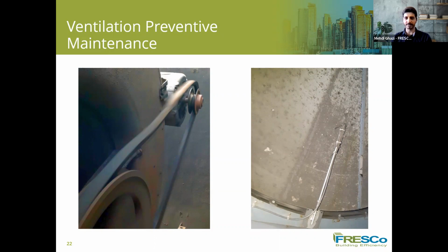At the right side, you can see a fully clogged central HRV core. It's a heat recovery ventilation system. You can see there are bugs and debris making it full, so the air is going to bypass the filter, and this can result in the coils and heat exchanger cores also getting full. So we will lose efficiency, and we will have lower supply air in our building.